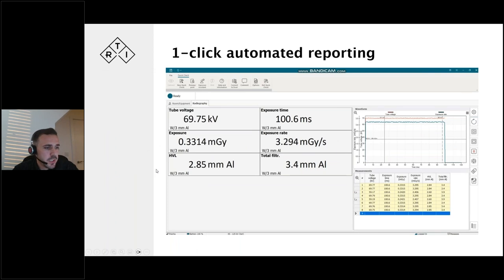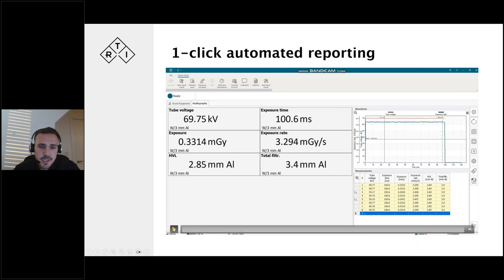The big advantage of using software in this application is that typically if you use a display device, even though it might be one click quicker, when you come to produce a report or produce the output of your testing, you then have quite a lot of manual data entry to produce. Typically people either write these figures down or use Excel, and one issue with that is traceability. It's also less efficient if you start writing numbers into Excel.